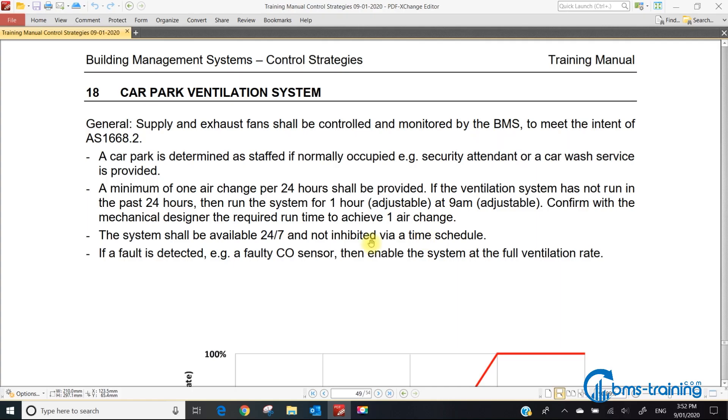The system shall be available 24/7 and not inhibited by a time schedule. The standard doesn't say that explicitly, but it doesn't talk about time schedules. Most functional descriptions will say the car park system is enabled between an occupancy time schedule, then controls to the CO. But the standard doesn't talk about a time schedule, so you probably shouldn't have one.